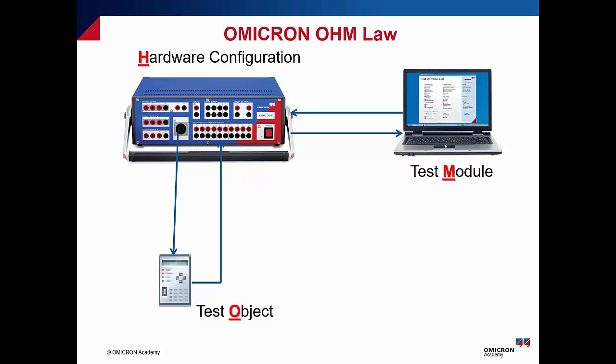Let's give you an example. We have here differential protection. For this differential protection, for sure, we have to apply the differential protection test module. It is not applicable to use distance protection, for example, or overcurrent in this application if we are testing only the differential function. Because as we know, numerical relays right now have a lot of protection functions in them. They have overcurrent, sometimes distance as well. In some countries, I saw that they apply distance protection in a power transformer to protect each winding, representing the winding as impedance. That's why they use distance protection to protect the winding, and at the same time they also use this function as a backup. But the main function is differential protection for sure.